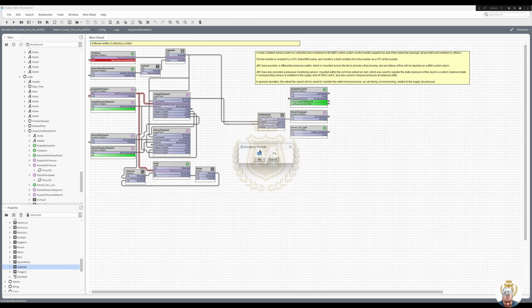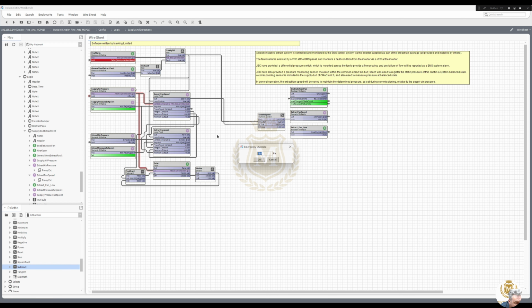Actions, emergency override, 750. Speed's gone back up again. That's still not in alarm. Actions, emergency override. It's 750 there. So if I go to 700 now, it should go alarm because it's too low. And then I want to wait.